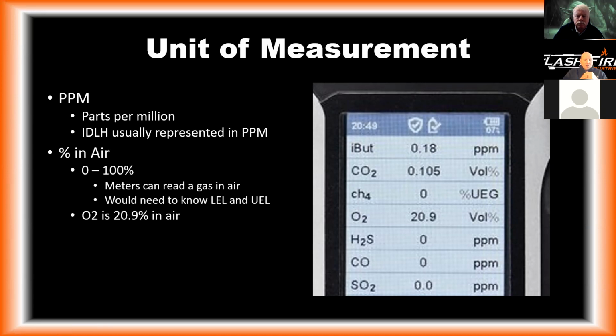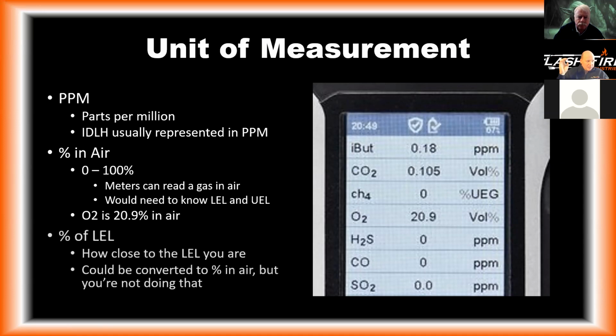Percent in air. We could have 0% oxygen in air. We could have 100% oxygen in air. We know that oxygen is 20.9%, 20.8%, about 1/5 of the atmosphere. So when we're talking about O2, it's reading that gas in air. There are meters that are able to read the entire gas in air, meaning it could read methane from 0 to 100%. That's not what your meter does. And that leads into percent of LEL. That's what your meter is doing.